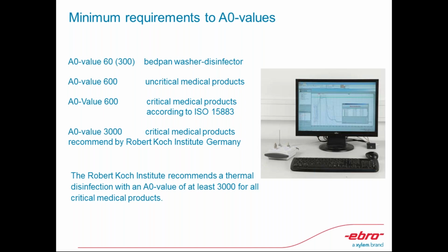So these are references of what is the acceptable disinfection values for bedpan washer disinfectors, for non-critical medical products, and for critical medical products, according to ISO 15883. The reason why I'm presenting this is your customers in the CSSD will really appreciate the software, because our software, the WinLog Med or the WinLog validation, can automatically calculate the disinfection values, just basing everything on the data acquisition process using the loggers.